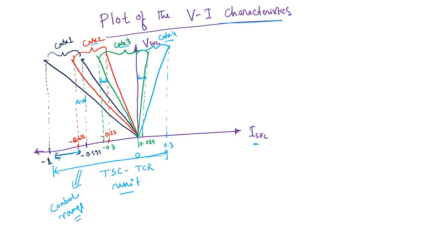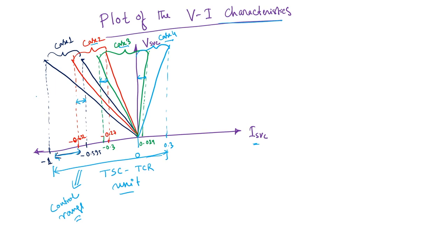It is possible to provide any value of this VAR, either VAR absorption or VAR production, by controlling the TSC and TCR units. And as you can understand, this is the maximum production limit of the whole TSC-TCR unit, and this is the maximum absorption limit of the whole TSC-TCR.